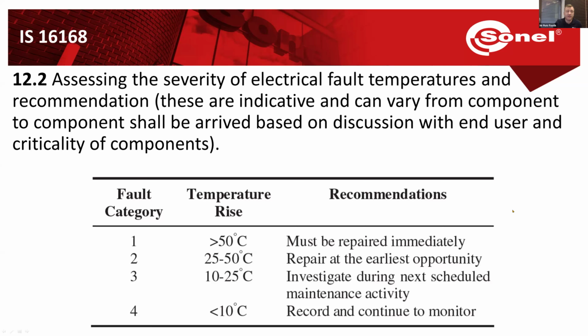Now, what is the expected value of temperature? Let's look at what happens in normal conditions—we can compare the three phases with each other if they have an even load, and we can check manufacturer specs of different breakers and connectors to make sure the temperatures we measure are within the right range.